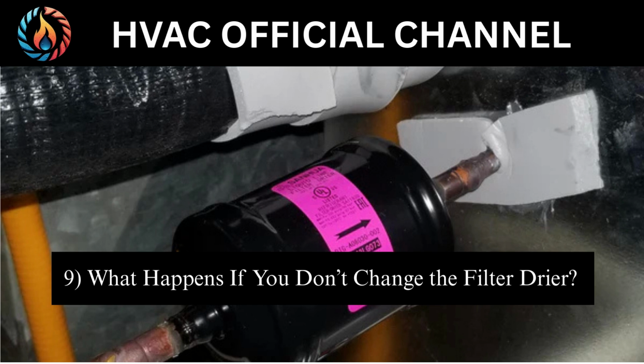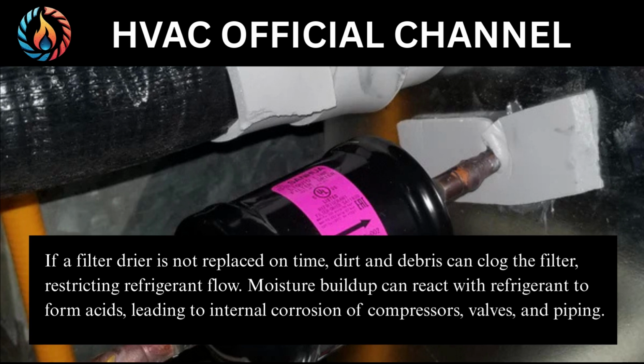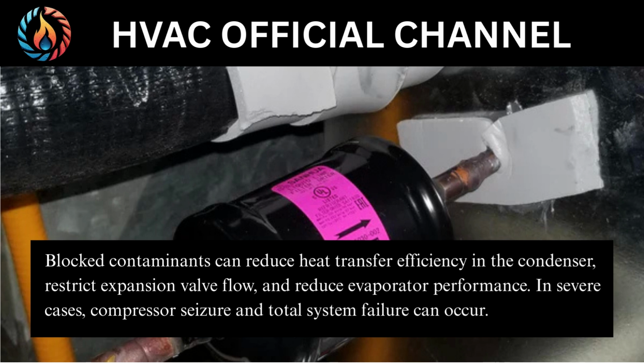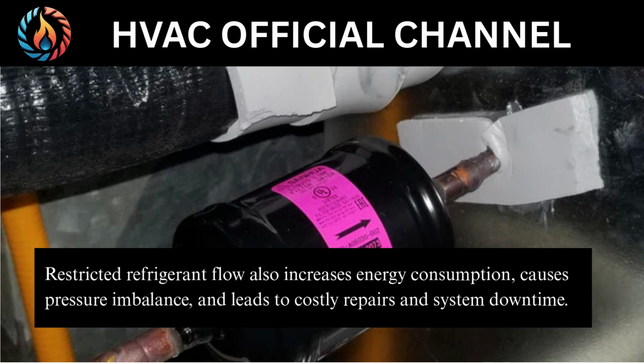9. What happens if you don't change the filter dryer? If a filter dryer is not replaced on time, dirt and debris can clog the filter, restricting refrigerant flow. Moisture buildup can react with refrigerant to form acids, leading to internal corrosion of compressors, valves, and piping. Blocked contaminants can reduce heat transfer efficiency in the condenser, restrict expansion valve flow, and reduce evaporator performance. In severe cases, compressor seizure and total system failure can occur. Restricted refrigerant flow also increases energy consumption, causes pressure imbalance, and leads to costly repairs and system downtime.